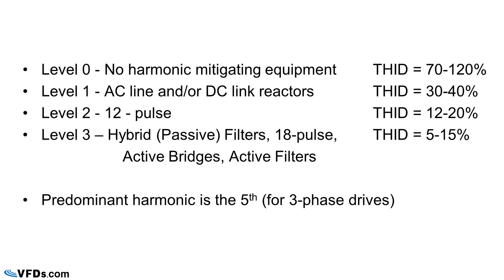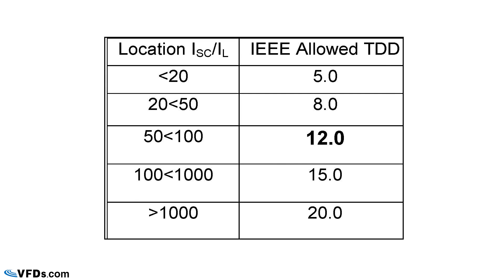So the question is, how good do we need to be? Take a look at this diagram from IEEE 519. If we have a very strong system — that would be an I short circuit to I load of greater than 1000 — they will let us have 20% harmonics. If we have a very weak system, that would be a system in which we have less than 20 short circuit to load ratio, and we have to maintain 5% harmonics. In reality, 95% of the systems will be in the 12 or 15% category. I've highlighted the number 12 — in 98% of the instances, if you keep 12% distortion, then you will comply with IEEE 519.